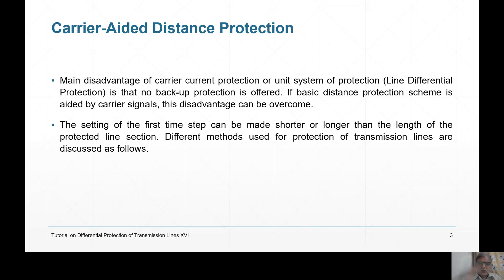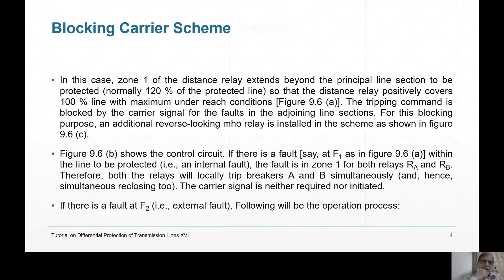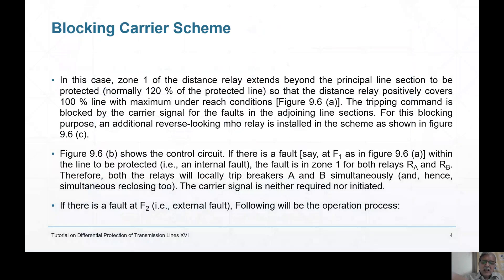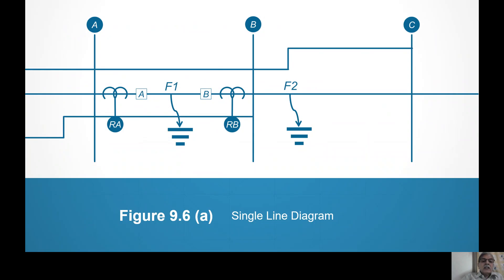The setting of the first zone may be shorter or longer than the length of the protected line section — it will be different as per different methods. Let us discuss the first case. This is a blocking carrier scheme. In the blocking carrier scheme, relays RA and RB are there. Line AB we want to protect. Our main aim is that breakers A and B should simultaneously trip and simultaneously reclose to avoid power system instability.